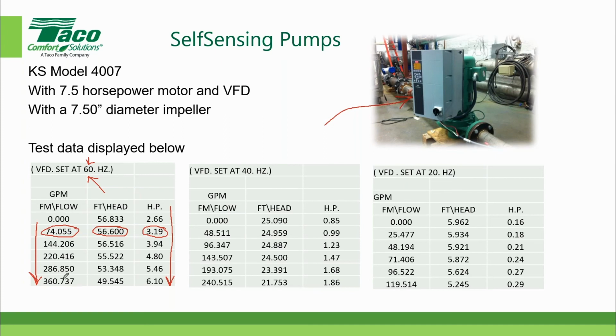So this data that was collected in the laboratory is then placed inside the drive. We actually physically type it in using a computer, and we type in all of the data. From that point forward, the software knows exactly what flow and head it's producing, because it can easily measure its own speed, which is an electronic piece of information, and its own power consumption. It looks up the other data that we stored in the drive. And that's fundamentally how a self-sensing pump operates. It knows its own speed, it can measure its own power, and it looks up the flow and the head.